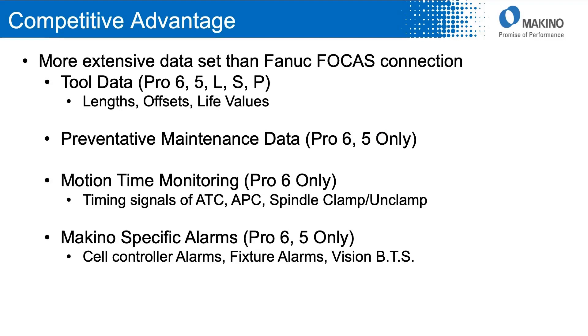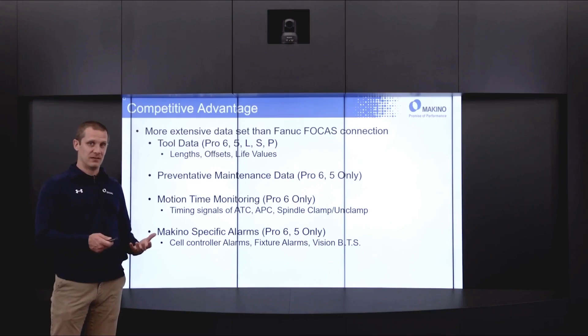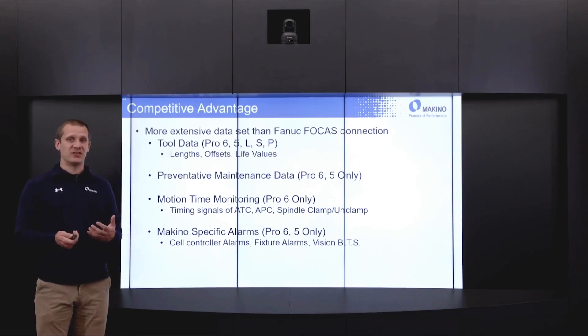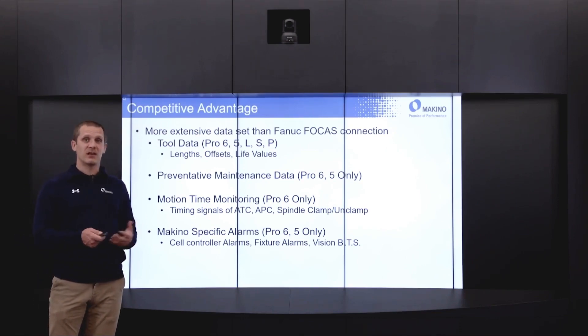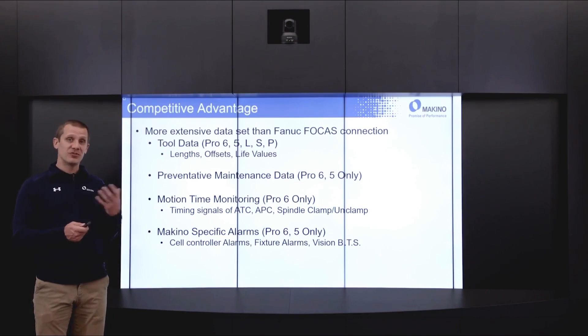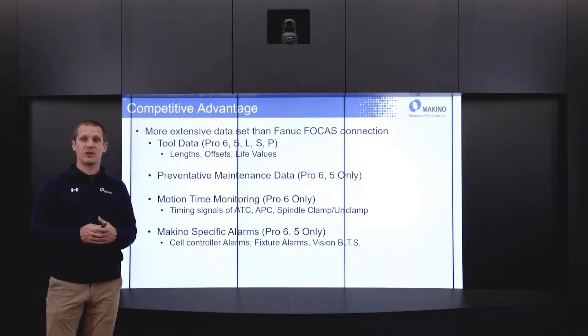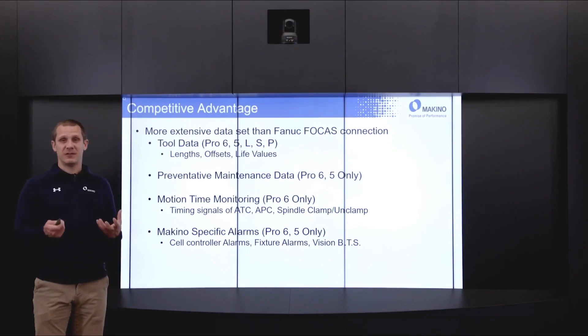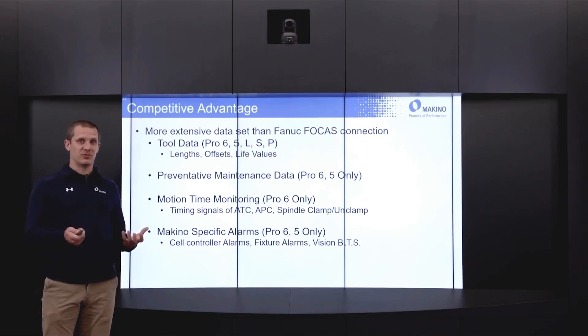One question I get frequently is why not just connect Makino machines with the FANUC FOCAS connection? The Makino Data Collector has an advantage over FANUC FOCAS — we're able to access additional information that a FANUC connection can't get. Things like your tool data on all the milling machines, your length and life values, your preventative maintenance data on some of our newer milling controls, motion time monitoring data which watches the timing of your tool changer, your pallet changer, spindle clamp, and Makino-specific alarms, notably in the cell controller space.